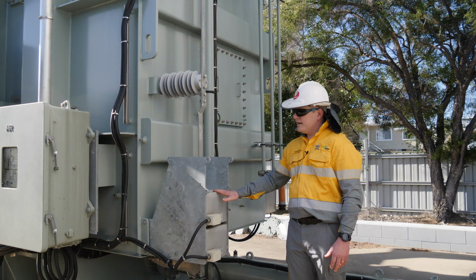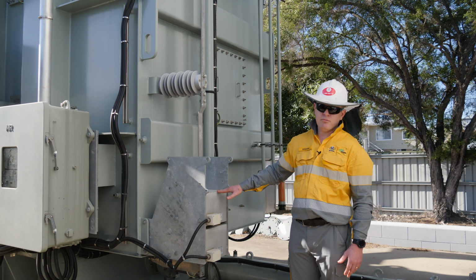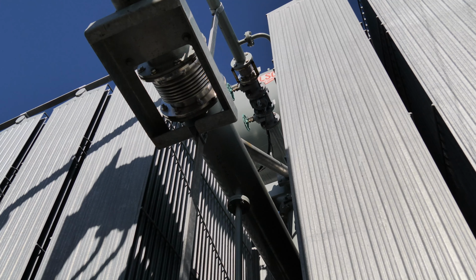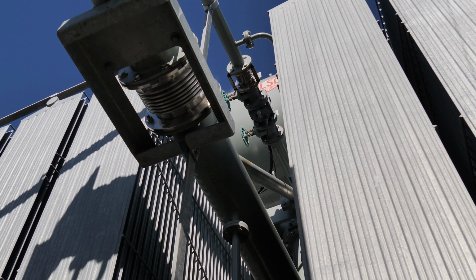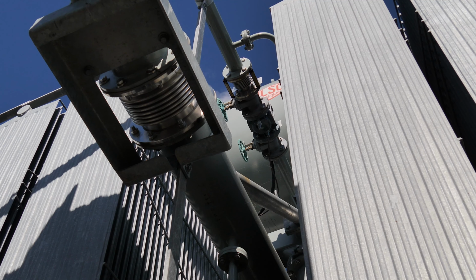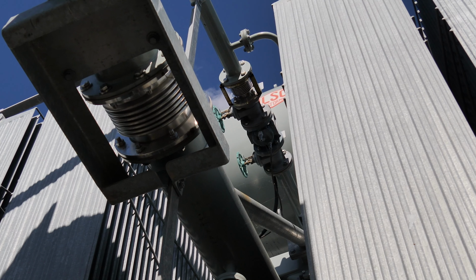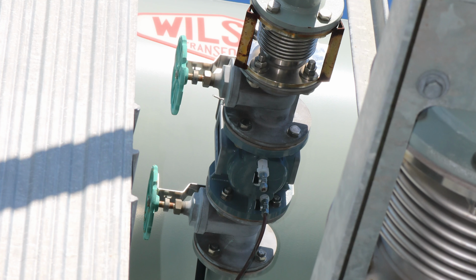These CTs will then provide inputs into the transformer protection scheme, and the transformer circuit breakers will operate to protect the transformer. Another protection scheme on the transformer is our Buchholz relay, and the Buchholz relay is on that main pipe heading into the conservator, and it's in series with the pipework. And the purpose of that Buchholz relay, which is located between those 2 green taps, is to detect any oil surges in the transformer. If there is a fault, an interwinding fault on the transformer, it will create a tremendous amount of energy and heat, and this will manifest as an oil surge that will run up the pipework and through that Buchholz relay. The Buchholz relay is set up or calibrated to detect any such surges, and it will then trigger the operation of the transformer circuit breaker in the event of an oil surge to protect the transformer and prevent a catastrophic failure.